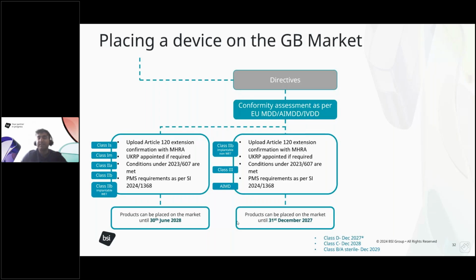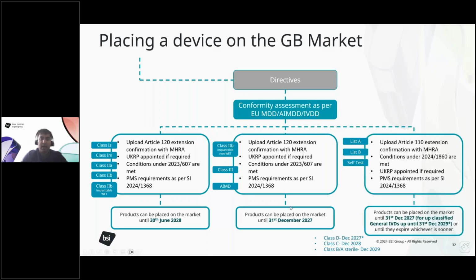From an IVD perspective, this again takes on board the requirements of 2024-1860, which Sarah quite rightly went through. But for the List A, List B self-test devices, you need to upload an Article 110 extension confirmation with the MHRA when you register. Make sure that the conditions under 2024-1860 are met. Appoint a UKRP as required. And again, the PMS requirements as per statutory instrument 2024-1368 have to be met.